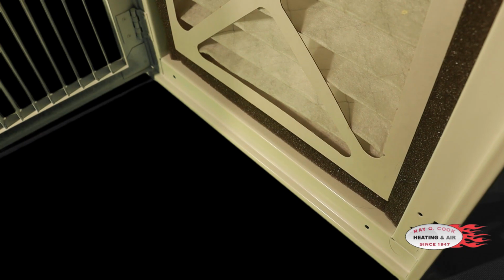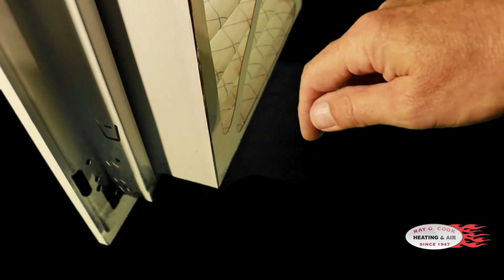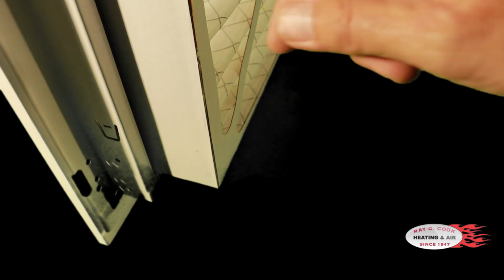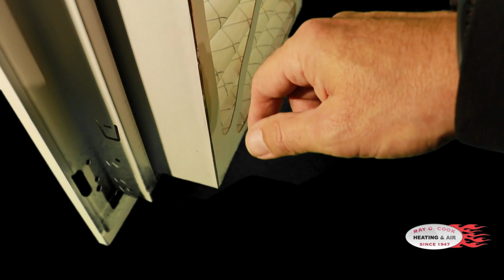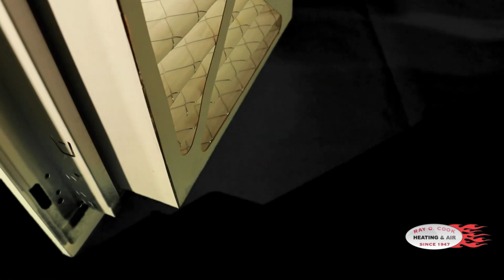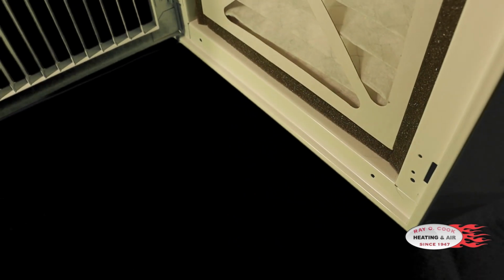But that's a 3-inch, and that's going to do a much better job for us, because it's got all that pleating, as long as it doesn't have bypass, and as long as we have enough area above it, minimum of 12 inches from the ceiling to the can here, to be able to draw the air through. At Ray O. Cook, we do almost 24 inches there, almost 2 feet, so that we can load and draw through all of that filter at an even rate, so that the particles go through the filter everywhere at the same rate. But that'll give you an idea on 3-inch filters.